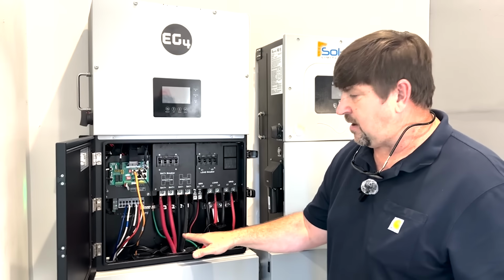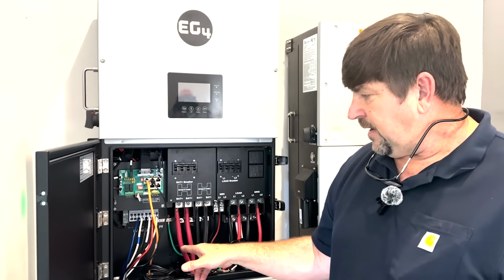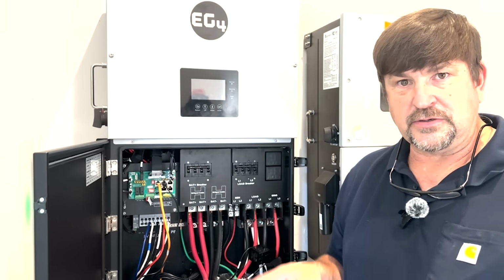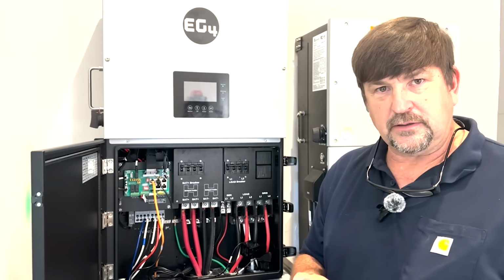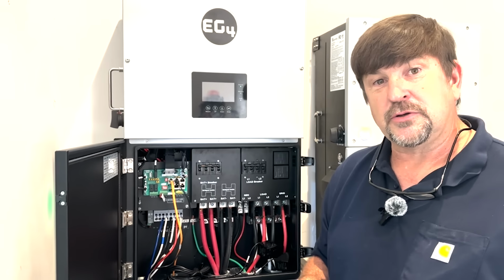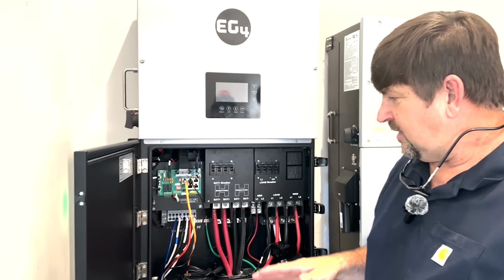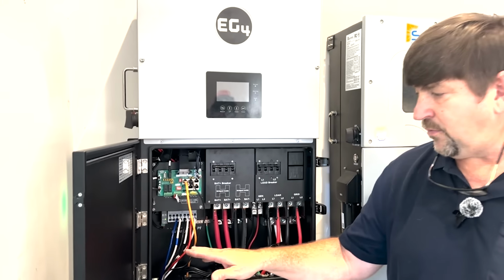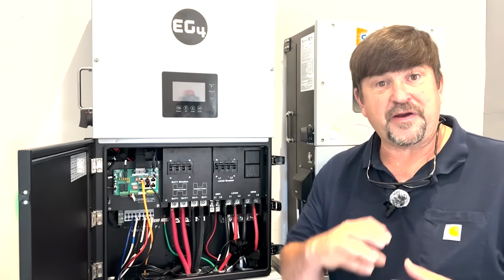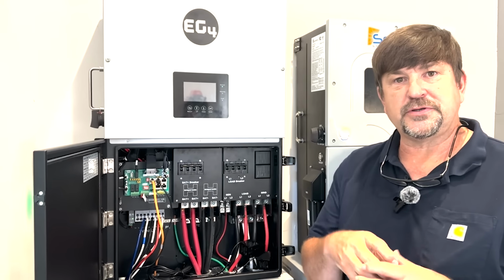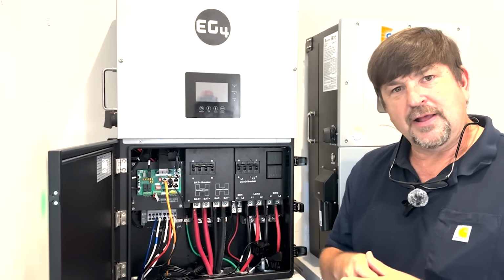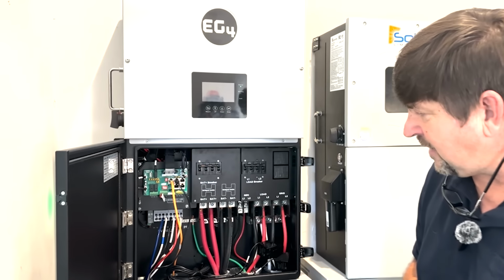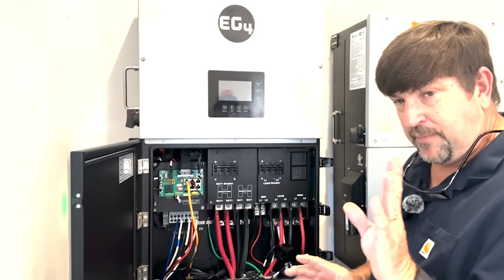In terms of commissioning, there were a couple things I did not like right off the bat. It kind of freaked me out to land high-stranded battery cables into mechanical lugs. I know it's legal and you can do it, but just because you can doesn't mean you should. Throughout their manual, they talk about using a ferrule wherever there's a stranded wire, crimping it down for equal distribution and better conductivity.